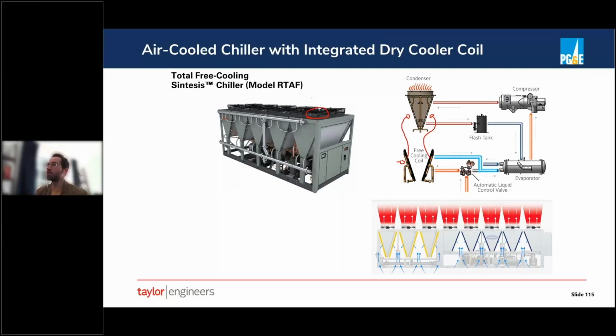So what you can see with some of these systems is conditions where these fans will actually slow down to maintain minimum head pressure. And in doing so, they reduce the amount of free cooling that they're providing. So there's a trade-off of using this integrated condenser and free cooling design.